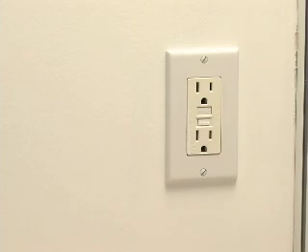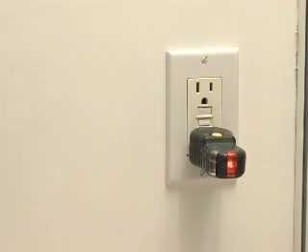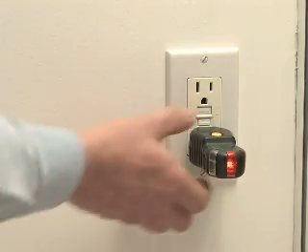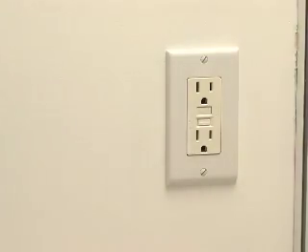After the moisture issues, we've got electrical issues. You need to make sure the outlet is ground fault protected. We have this bit of equipment which sets up a false trip on the ground fault just to make sure that it's operating. A lot of homeowners are not necessarily aware that this item is a safety device. It's designed so that if you drop something electrical in the water, it will trip the switch rather than give you a shock.